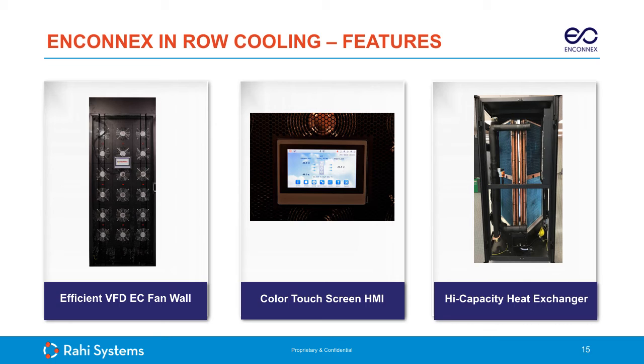So yeah, it's designed with some best of breed components. The variable speed EC fans are selected from EBM Pabst, a very widely known manufacturer, and easy to source. And then the color touchscreen, the HMI, is very easy to use. The heat exchanger is a microchannel coil. Interestingly enough, it's a V coil on the chill water unit specifically. It's got a much higher capacity, as we talked about. And that blue color you're looking at is a hydrophilic coating, which actually captures condensate and moisture, so there's no moisture carryover, which is key. So a couple more components on the next slide here.